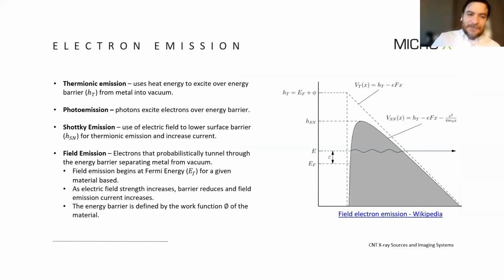So by way of introduction, to make an X-ray, you need an electron current. And when electrons are in a metal at rest in a vacuum, there's a barrier. That barrier prevents the electrons from escaping into the vacuum. So typically, electrons are given energy through thermionic emission. Heat energy is input into those electrons that allows them to move over that barrier and create a current. That current is then used to make X-rays by accelerating it in a potential in a vacuum.